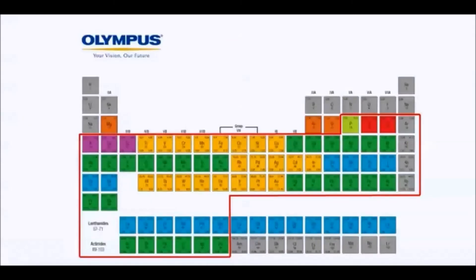Elemental limits run from phosphorus to plutonium. Typically, based on customer needs, analyzers are set up to measure from titanium to bismuth. By the end of the calendar year, the elemental range will be extended to aluminum as an alloying material in iron, copper, nickel, or titanium grades.